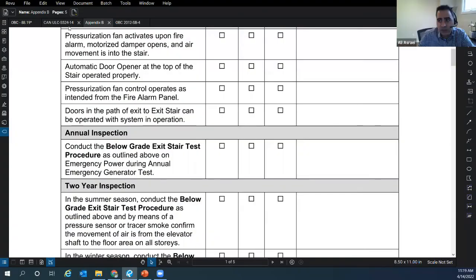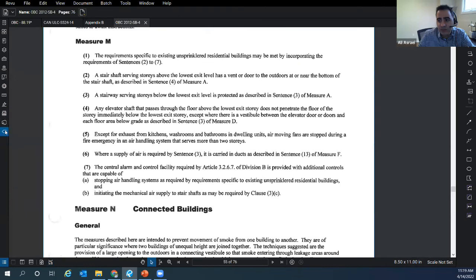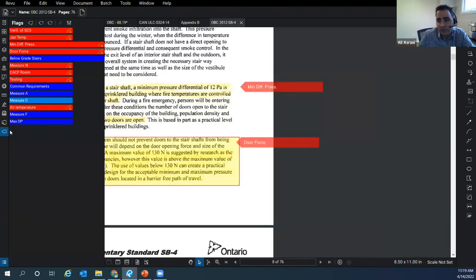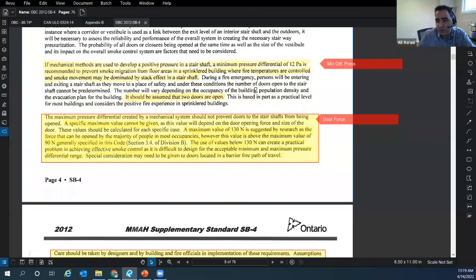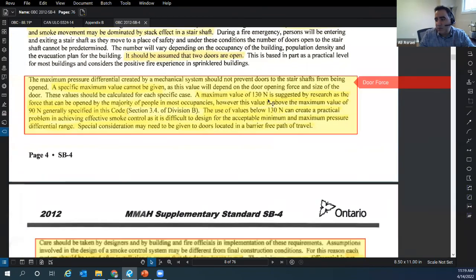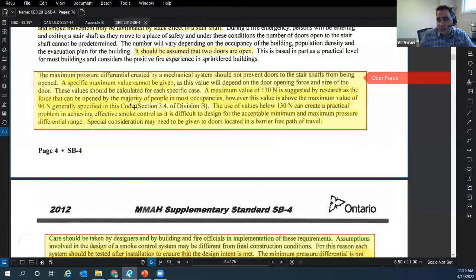That's great. Yeah, that's great. Because SB-4 again, I think I have that here for the door force. See, the writing is: the maximum value of 130 newtons is suggested by research as the force that can be opened by the majority of people in most occupancies. However, this value is above the maximum value of 90 newtons generally specified in this code. The use of a value below 130 newtons can create a practical problem in achieving effective smoke control, as it is difficult to design for the acceptable minimum and maximum pressure differential range.